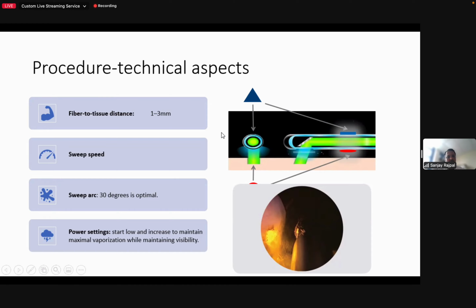The next thing is to maintain the fiber to tissue distance, which is approximately 1 to 3 millimeters. A good visual cue is the metal cap in front, which is easily visualized through your camera, and that's about 1.8 millimeters. So that's the distance you need to keep from the tissue. If you're too close to the tissue, the heat will cause damage to the laser fiber, and if you're too far away, you cause more coagulation than vaporization. So having the optimal distance is important.